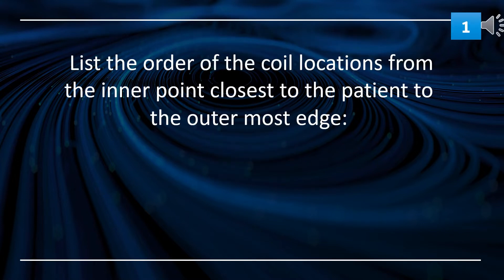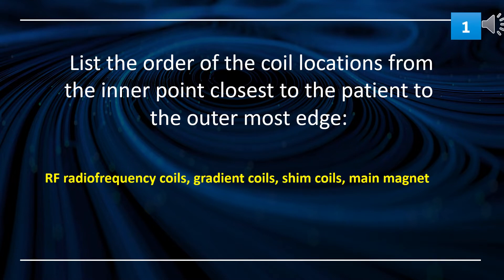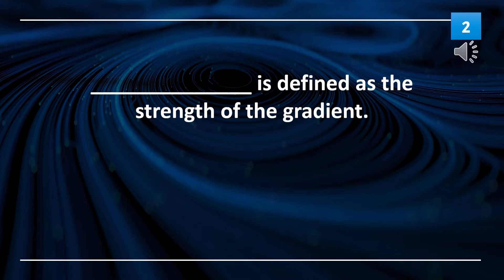List the order of the coil locations from the inner point closest to the patient to the outermost edge. The radio frequency coils are closest to the patient, then gradient coils, then shim coils, and furthest is the main magnet.